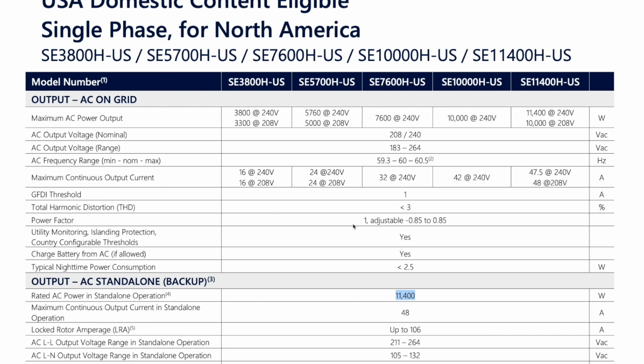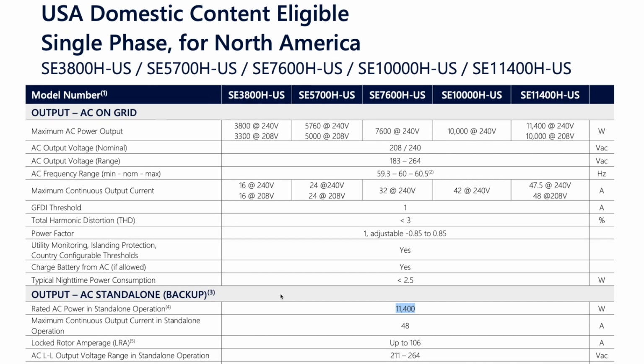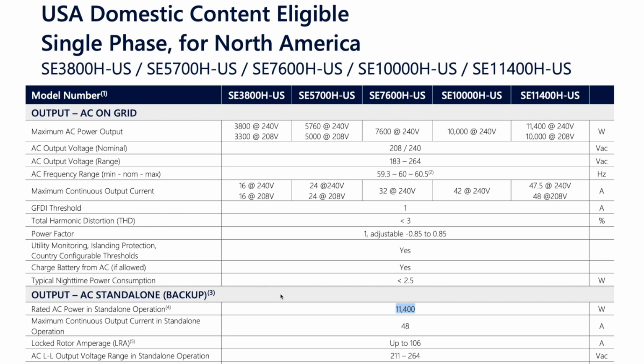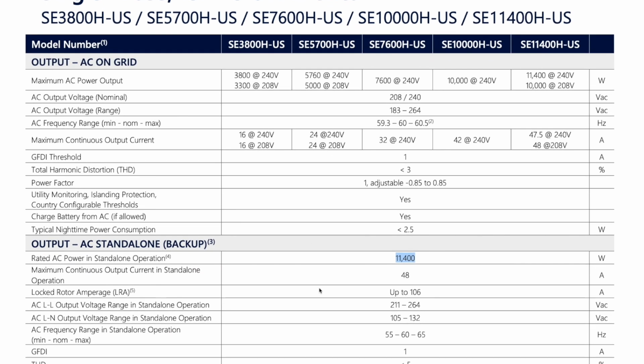Rather than trying to change your design guidelines between if it's a domestic inverter or a foreign inverter, in my opinion, it's not that much more cost. The easiest thing to do would just be to go 63 amps and number 6 across the board for any SolarEdge backup configurations. And that way you just always know when the system goes into backup mode, no matter which inverter you have, you're not going to end up having that breaker trip, causing a power outage on the homeowner during their outage and resulting in a service call.